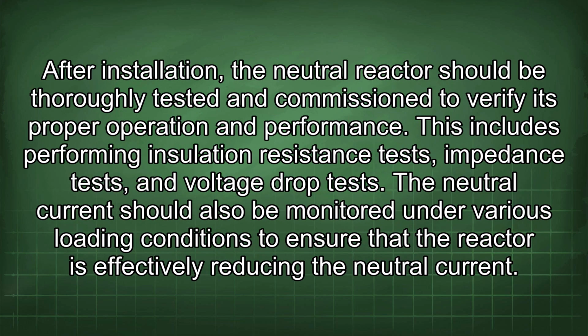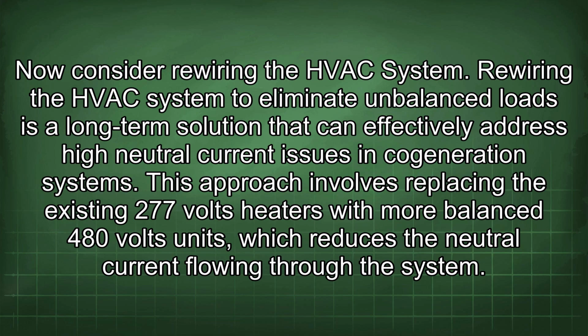After installation, the neutral reactor should be thoroughly tested and commissioned to verify its proper operation and performance. This includes performing insulation resistance tests, impedance tests, and voltage drop tests. The neutral current should also be monitored under various loading conditions to ensure that the reactor is effectively reducing the neutral current. Now consider rewiring the HVAC system.